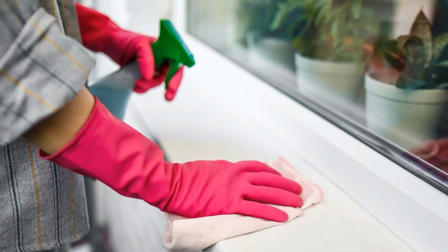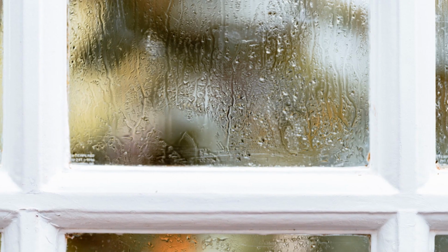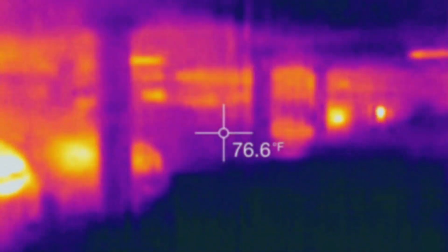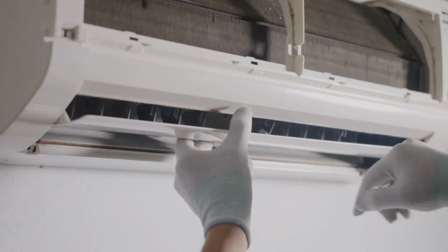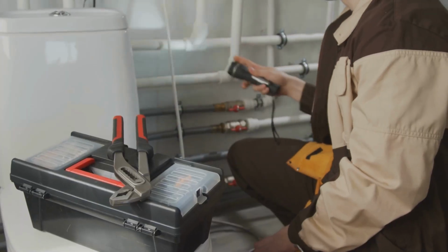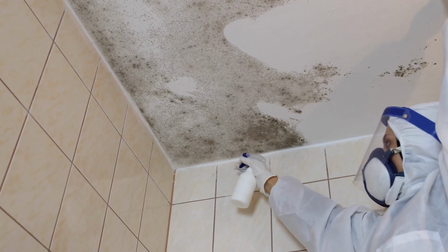Imagine a contractor walks into a bedroom and finds visible growth around a window. The easy assumption is that the window leaked. But what if the issue is actually condensation caused by indoor humidity? What if the window frame is cold and the indoor air is holding too much moisture? What if the HVAC system is not controlling humidity properly? What if furniture was placed tightly against an exterior wall, limiting air movement? Each of those situations may produce a similar visual result, but the solution may be very different.